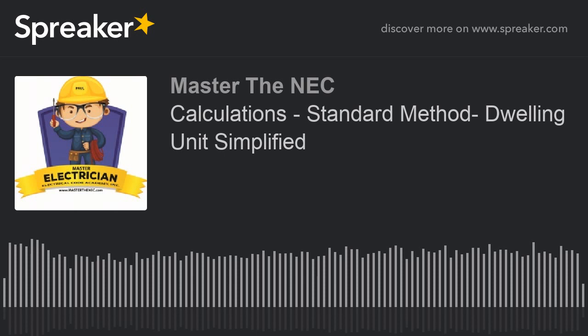Now, one thing I want to bring your attention to. This 220.53 says that it shall be permissible to apply a demand factor of 75% to the nameplate values, which is what we just did, when you've got 4 or more appliances that are fastened in place. And we're not including things like the electric range, clothes dryer, space heating equipment, or air conditioning equipment, okay? We have a different calculation for those things. We're just dealing with the other appliances that are fastened in place.